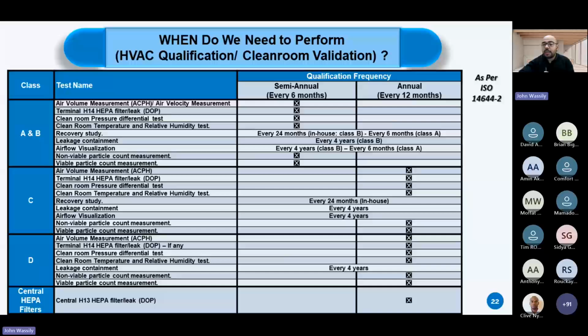Because it's not only that we will perform the qualification initially. If you can remember the diagram of the life cycle of the qualification, it's also repeated periodically in order to build confidence that the initially qualified state for the utility, for the equipment, and for the systems in general is always maintained throughout the entire life cycle of the system. So periodically, they shall be tested, either here as per the ISO every 6 months or every 12 months.